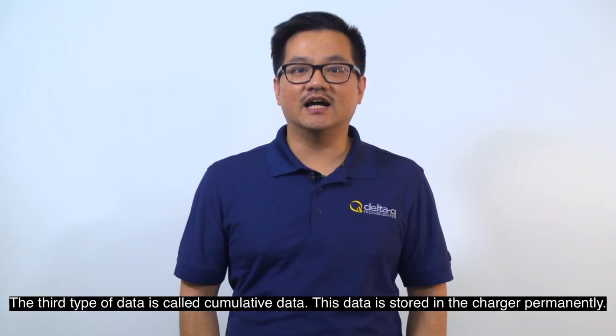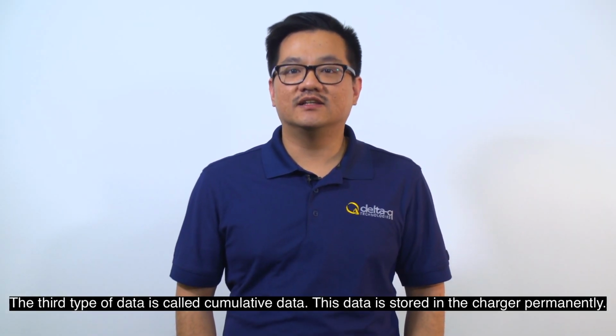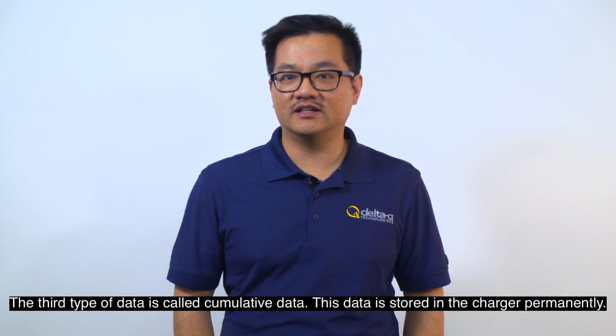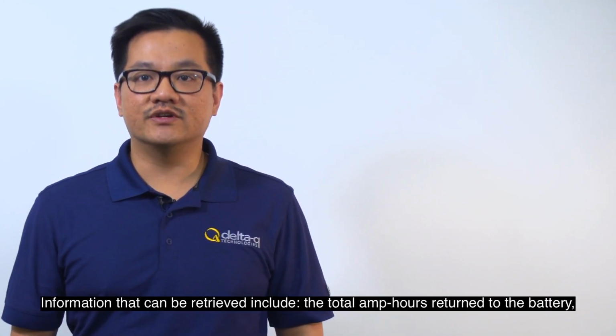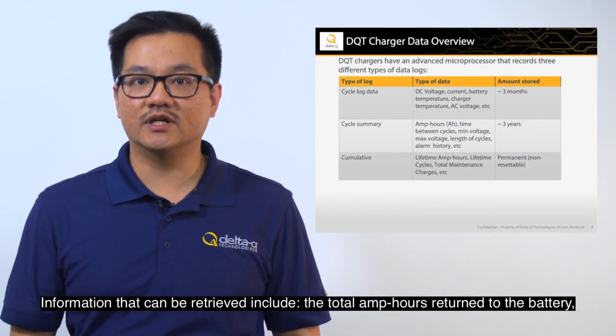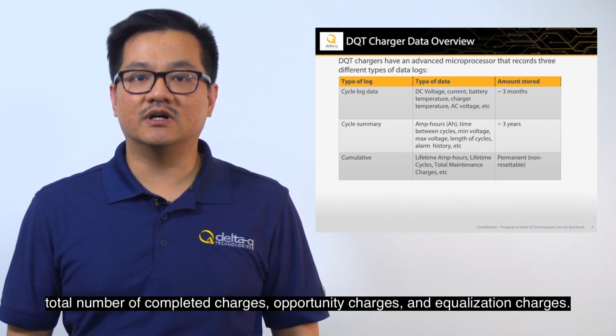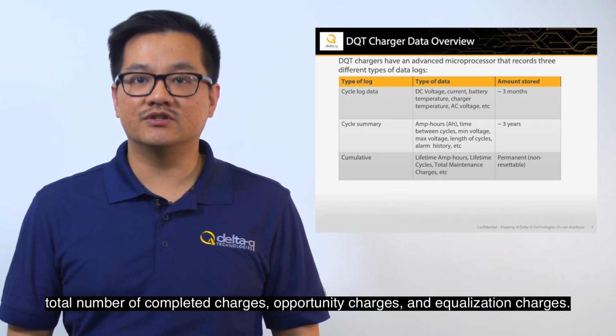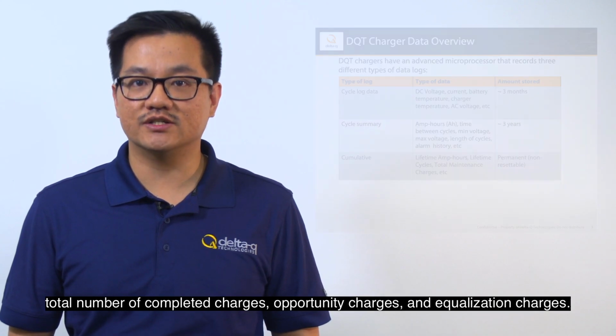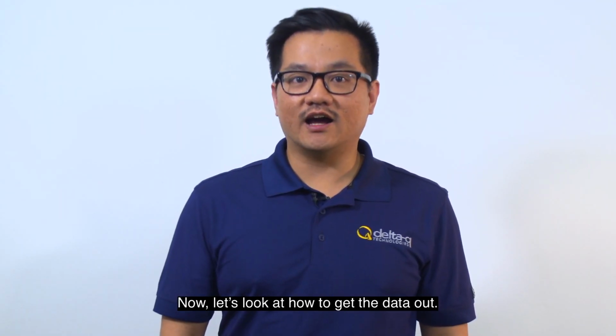The third type of data is called the cumulative data. This data is stored in the charger permanently. Information that we can retrieve includes the total amp-hours returned to the battery, the total number of complete charges, opportunity charges, and the equalization charges. Now let's look at how to get the data out.